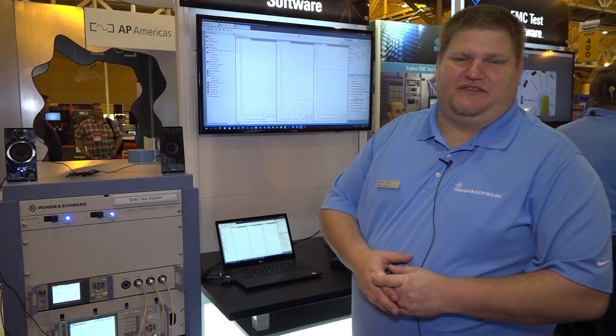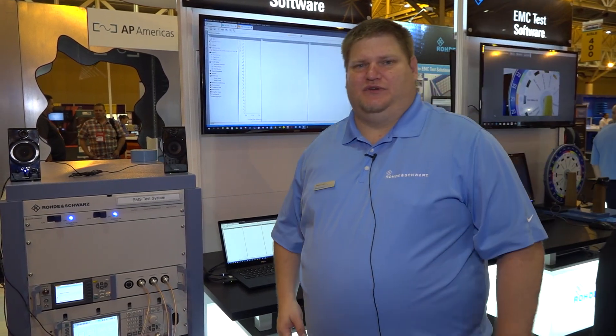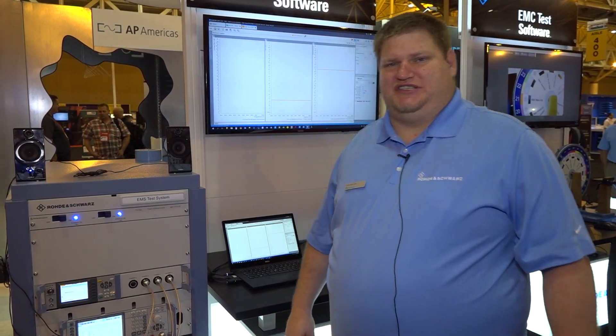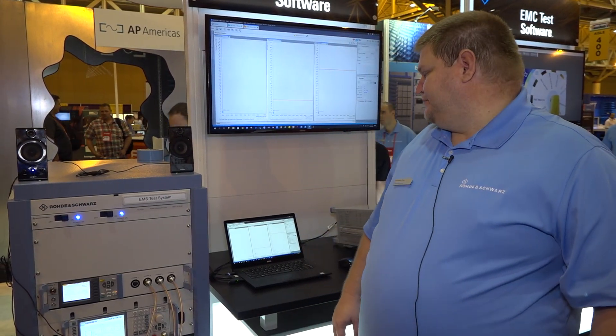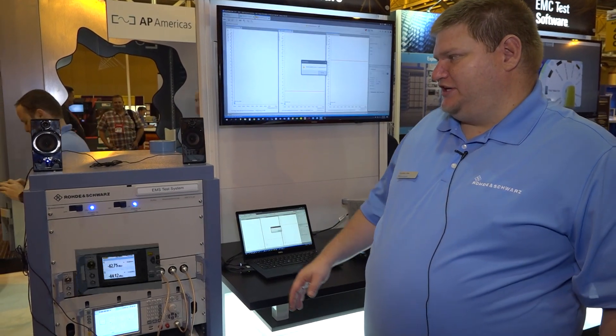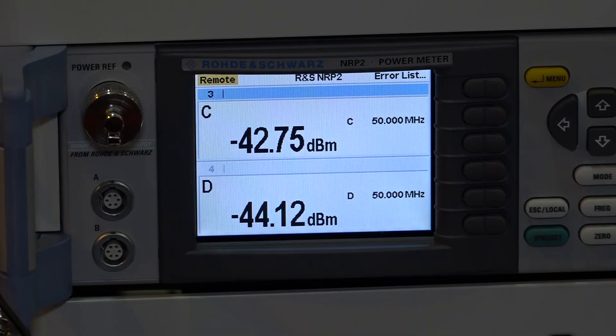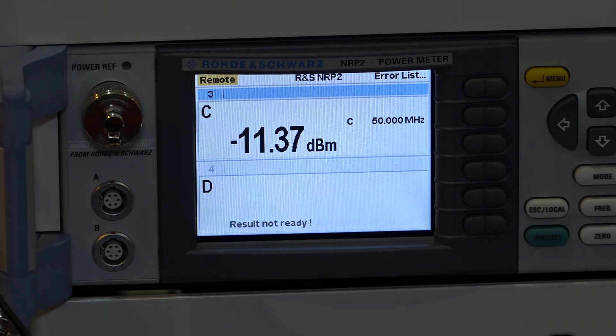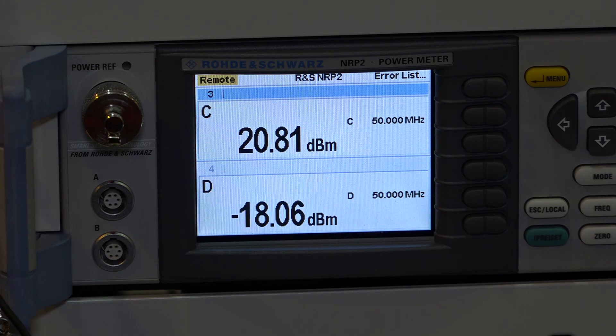This test is currently running from 50 megahertz to 100 megahertz during a BCI test. As the test begins to level up you'll begin to hear an audio signal because we're doing an AM modulated test. We'll hit OK to enter amplifier and to operate.